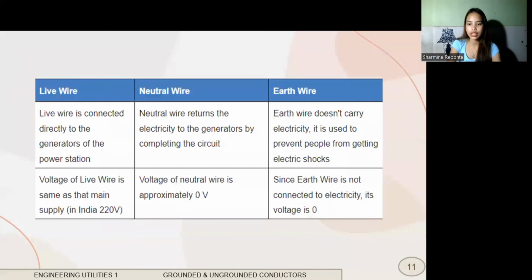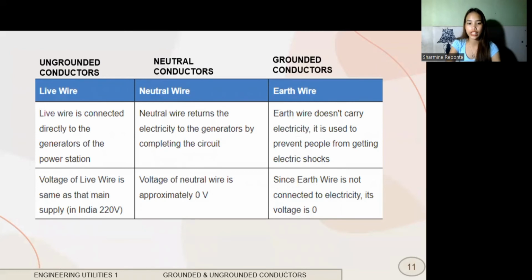I have here a table para mas dali na ito masabtan, para mas dali na ito ma-differentiate ang tatlo. Under ungrounded conductors, or what we call live wire, is connected directly to the generator of the power station. While the neutral conductor or the neutral wire returns the electricity to the generators by completing the circuit. So, neutral wire is ginabalik na daw ang electricity sa source niya. Grounded conductors or ginatawag nato nga earth wire doesn't carry electricity. It is used to prevent people from getting electric shock. So, mao lang yung purpose sa atong grounded conductors.